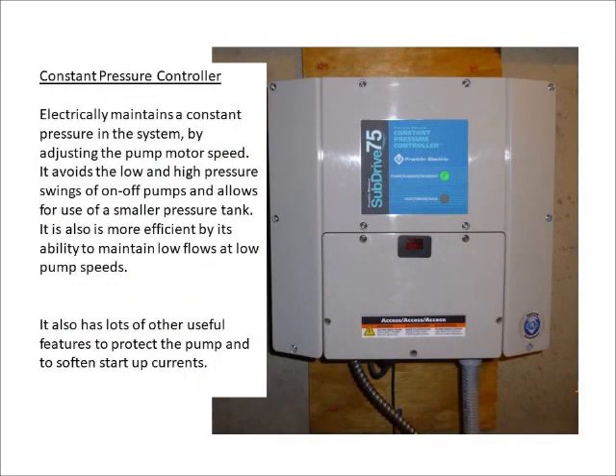This is the constant pressure controller. It controls the pump at the bottom of the well. It electrically maintains a constant pressure in the system by adjusting the pump motor speed. It avoids the low and high pressure swings of typical on-off pumps and allows for use of a smaller pressure tank. It is also more efficient by its ability to maintain low flows at low pump speeds. It also has lots of other useful features to protect the pump and to soften startup currents.